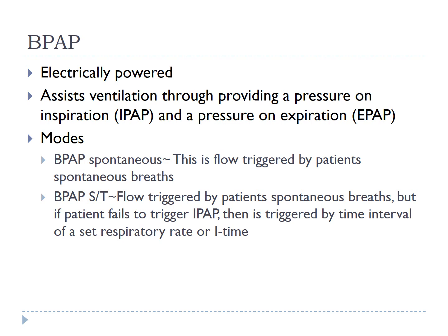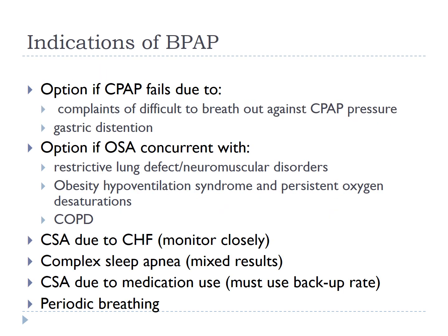This is flow triggered by the patient's spontaneous breath, but if the patient fails to trigger the IPAP, then it is triggered by a time interval of a set respiratory rate or I time. So this means you can have a set rate of 12. So if the patient doesn't take 12 breaths in a minute, the machine will deliver a breath. Let's go on. Indications for bilevel therapy.